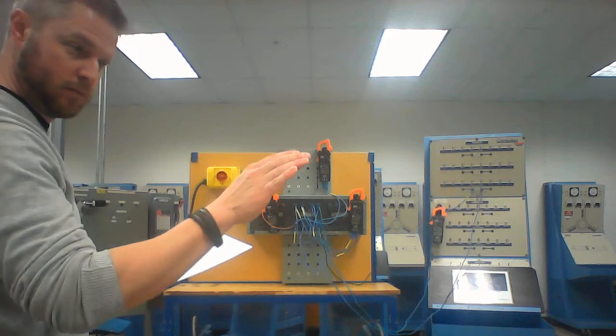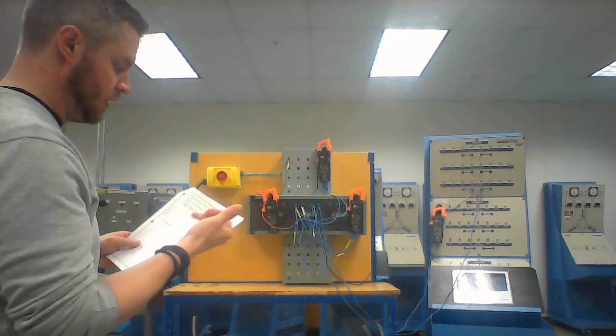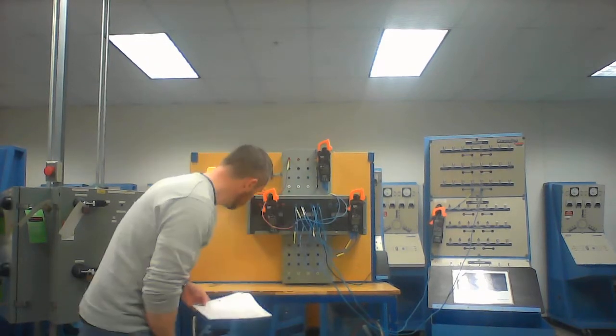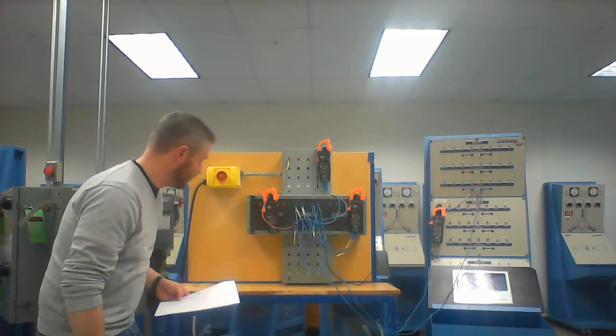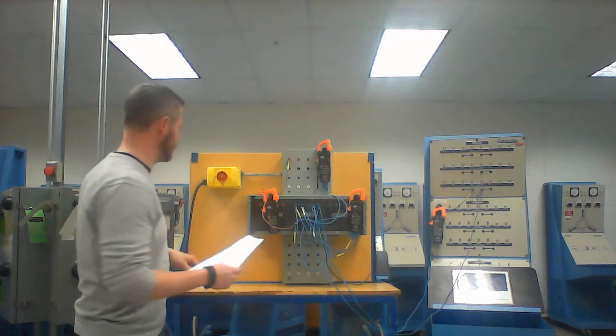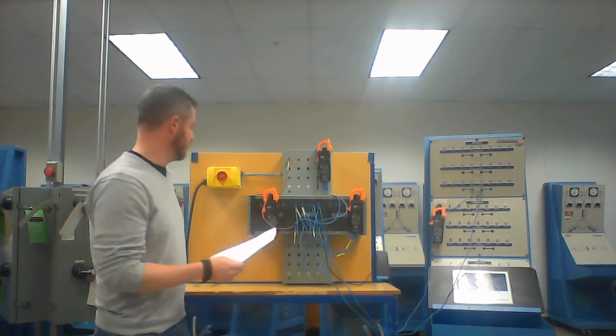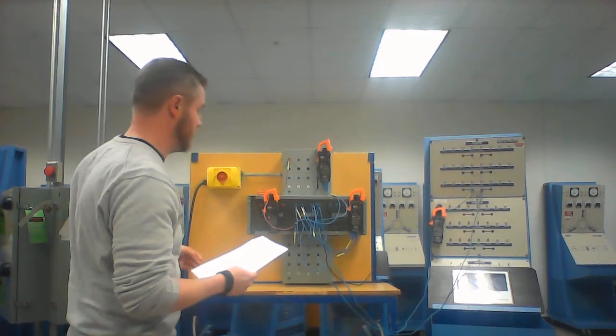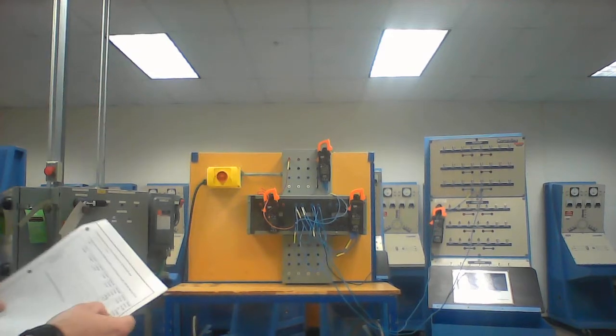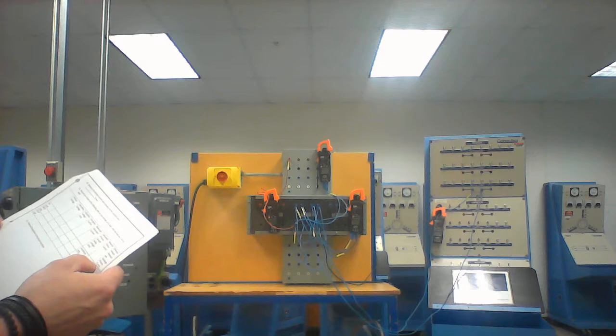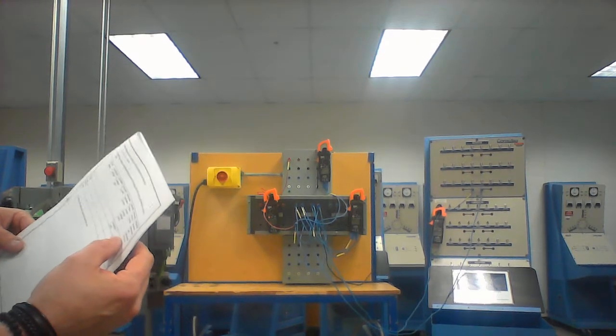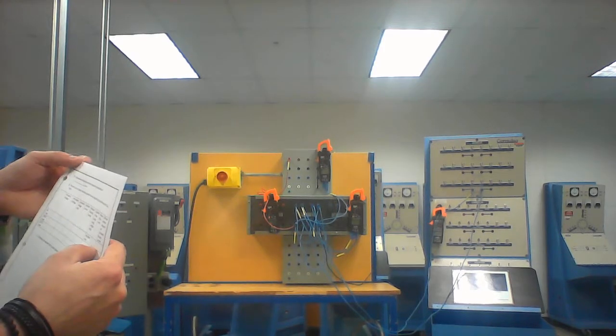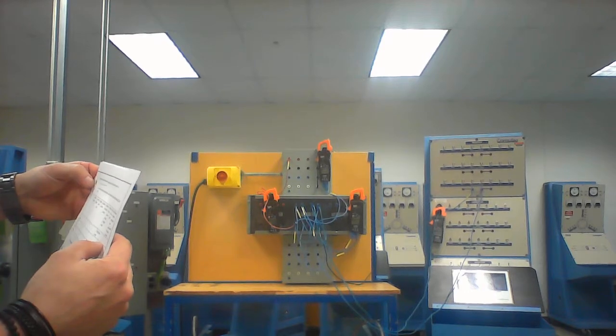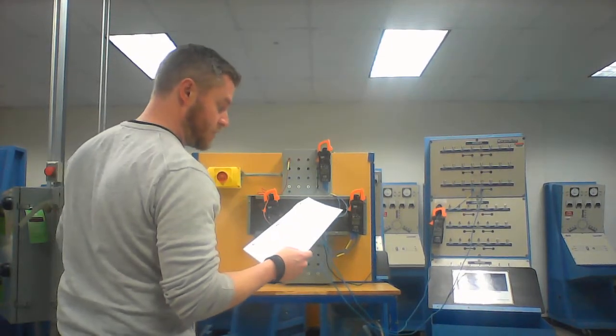Secondary current with no load. No current. Okay. Excitation only. Measured primary current, 0.75 with 5 turns. What am I measuring now? I'm just measuring excitation now, right? Yeah, no load. Measured primary current, no load. We're at 0.78. Oh, but that's the different side. Oh, that was with the load. One second. There we go. Okay. Good. No load, measured primary current, that's only excitation. We're good. Okay. Put that 440 back on.